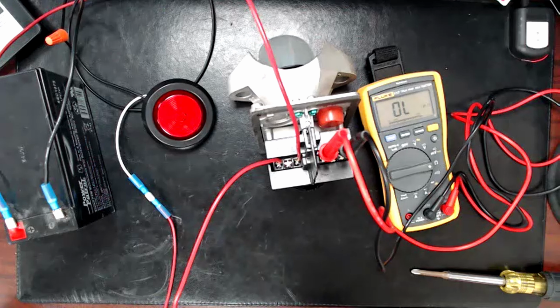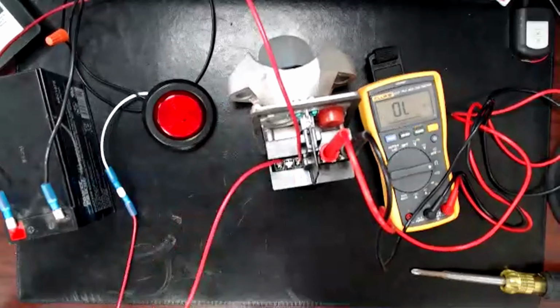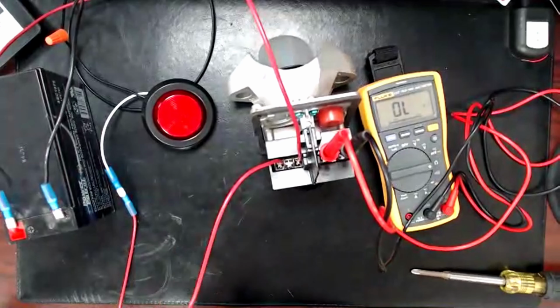But a lot of times when we do that dedicated sprinkler monitoring, we put in a cellular dialer with it, and the Starlink ones we use are powered by 24 volts. So if we're using one of the 24 volts for that cellular dialer and the other output is going for the horns and strobes, we have to have a way to trip the bell. So knowing how to do it this way, you can use that same 24 volts powering up that dialer, because it has the same battery backup, all the same everything. You can grab it, wire up a water flow this way, and even though there's only 2 outputs on the panel, you can accomplish 3 different tasks with it by knowing how to wire things this way.